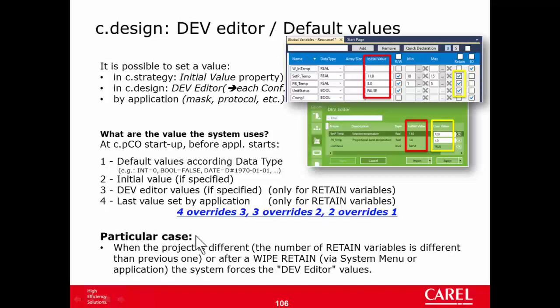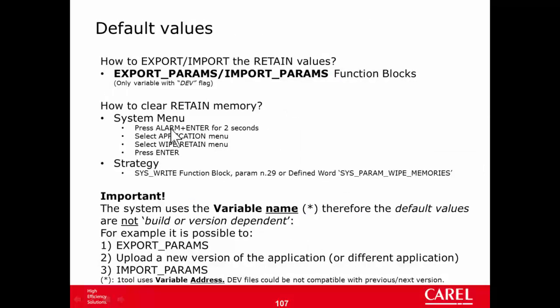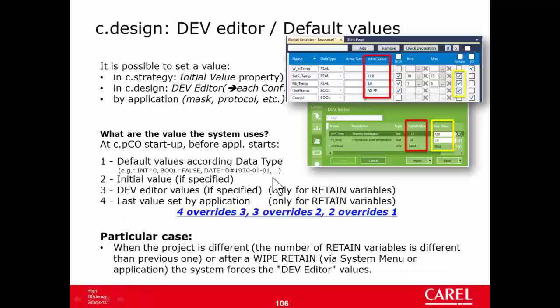Another use case is when the project is different — for example, the first time I upload the chiller alarms project into a controller that was running the chiller project. In that case, the system forces the DEV editor values, so the default values are automatically uploaded. The same applies in case of wipe-retain. It is possible to wipe the retain via the system menu: enter the system menu, hold alarm enter for two seconds, select Application Wipe Retain, press enter. When you wipe the retain memory, the system automatically installs the default values.